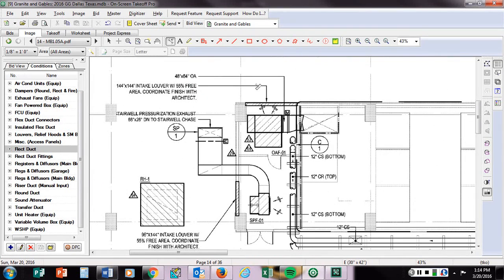That outside air fan is going to be pulling air through this louver. It's going to come into the fan, go horizontal, across and down. I would take this 48 by 84 outside air and just take it all the way across.